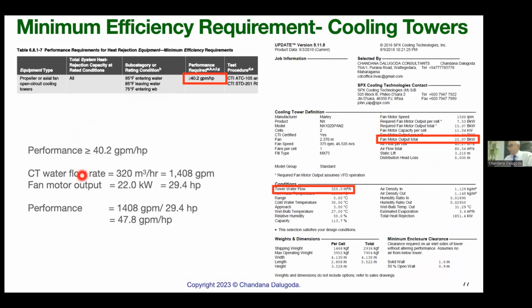The cooling tower water flow rate we selected is 320 cubic meters per hour, converted to 1,408 gpm. The performance value is 47.8. So it is above 40. So this is compliant. See, you can't just purchase cooling towers.